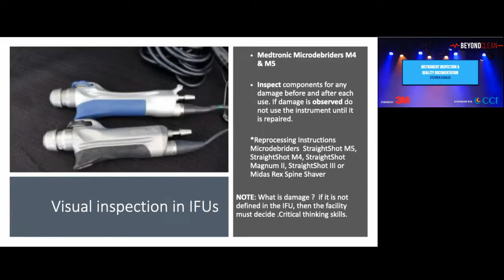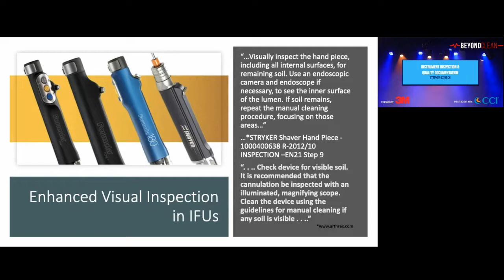Or this shaver: visually inspect the handpiece, including internal surfaces, for remaining soil. Use an endoscope camera and endoscope if necessary. Or this IFU: check the device for visible soil. It is recommended that cannulated devices be inspected with an illuminated magnifying scope. So what if you have 4 or 5 different companies and 2 are saying this and the others don't? You work with your risk management, your IP, and you put a good policy together, because you need to check them all the same way, because maybe those other ones just say inspect to make sure they're visually clean. And if you're using one way for one, you should be able to use it for the other. Make sense? Inspection, inspect. What are you doing to make sure it's the same across your instruments and medical devices you're using?